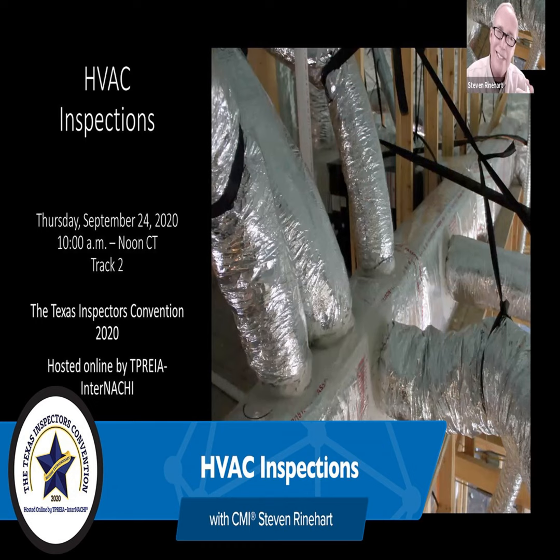Same exact absence of a floored passageway. Other requirements: noticeable vibration, blower and fan, real old ones. You pull the cover off an old Rheem or something like that, an electric unit, and you look at that blower, it's a big squirrel cage blower and it's just vibrating.